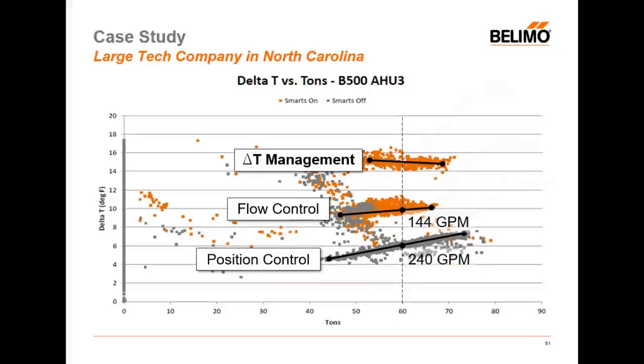And if I then include with my flow control delta T management, and now I'm really homing in on the efficiency because I'm managing the delta as well as the flow, and that's important because it's not the design condition every day. The temperatures do vary in the Middle East, and we're at light load for a considerable part of the year. Then I'm only going to need 96 gallons of water.